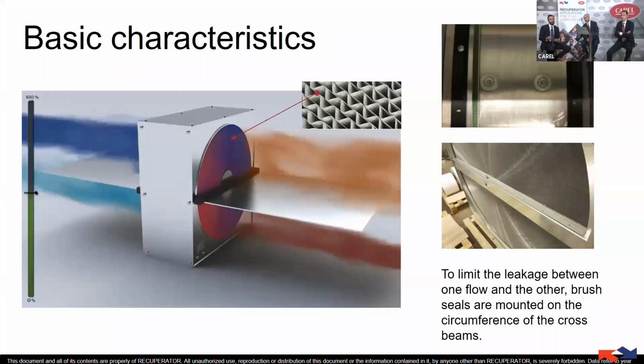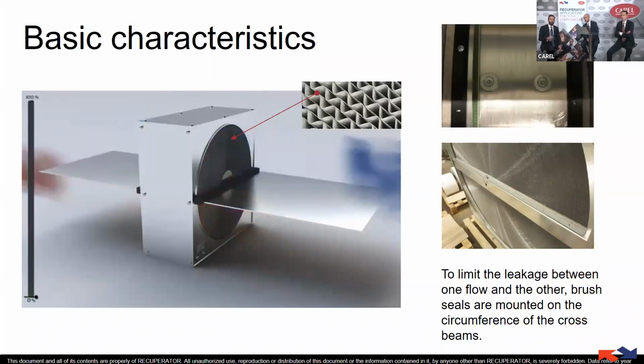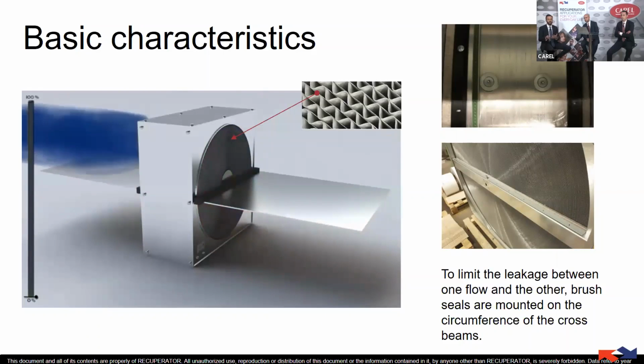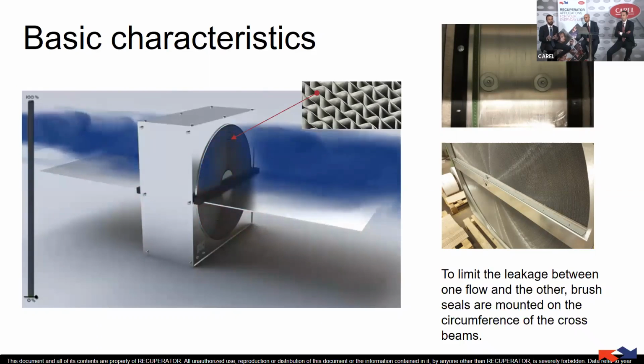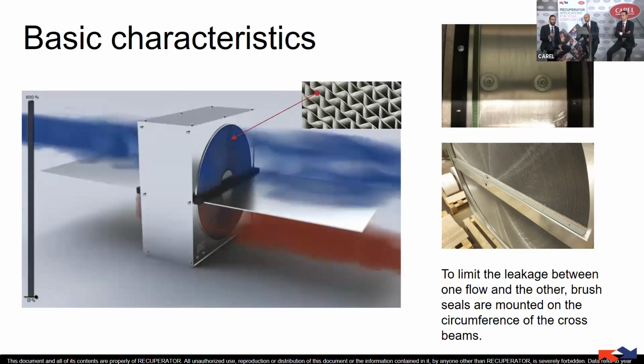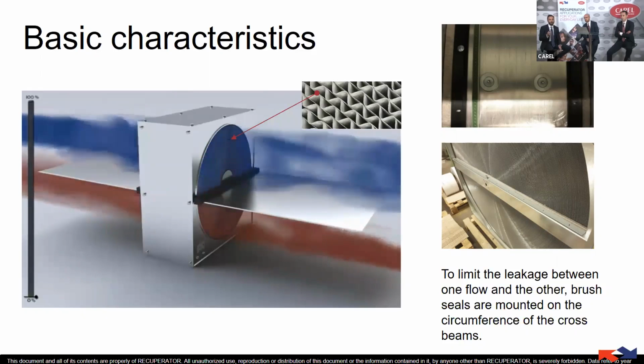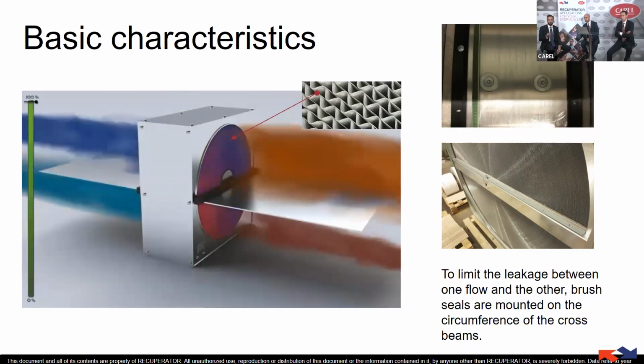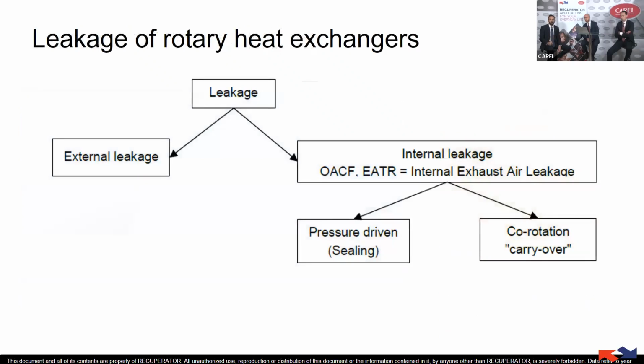But since this is a moving component, we have to cover the gaps created between the rotor and the casing with gaskets, something that can block any type of leakage. Let's go a little bit more into this topic, the leakage inside the rotary heat exchanger. In this slide, we can see two different types of leakage: external leakage and internal leakage. The external leakage belongs more to the unit; it is the air that passes through the sides of the rotary heat exchanger. Now we should focus on the internal leakage.